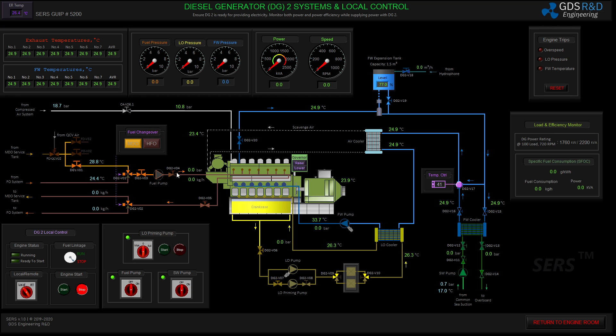I would like to line up the fuel system and start the fuel circulation, then the lubricating oil system. I am waiting for the fuel pressure to stabilize around eight and a half bar. Now I can start my lubricating oil priming pump.